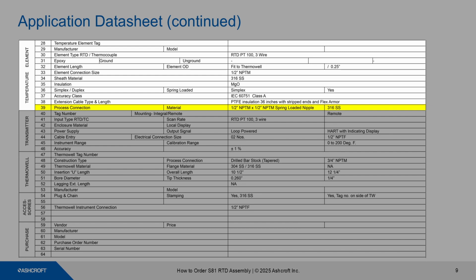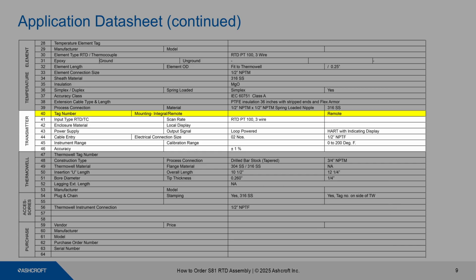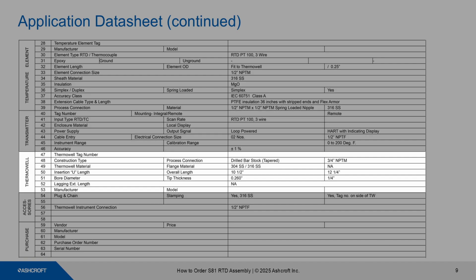Now we're going to look at the transmitter requirements. This is a remote mount transmitter. It's going to have HART and an indicating display. It'll be loop powered, and it's going to have a range of 0 to 200 degrees F. Now we will look at the thermowell requirements. It's going to be a threaded 3/4 inch thermowell, tapered. It's going to be either 304 or 316 stainless steel. We're going to select 316 stainless steel. It has a U dimension of 10.5 inches and an overall length of 12.25 inches. There is a requirement for a tag.